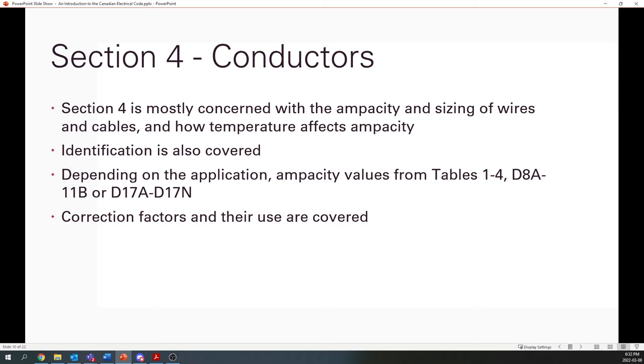It also covers identification of wires. And then it will direct you to a variety of tables, both tables giving ampacity values, such as these ones here, 1 to 4, and the ones which are used for more specialty cases, as well as correction factors. So we'll do an example at the end here to do with conductor sizing, and you'll hopefully get a better idea of what table you're going to use in what application or situation, and how to use correction factors for a variety of situations.